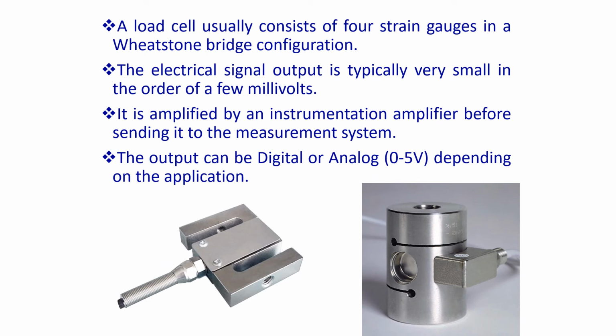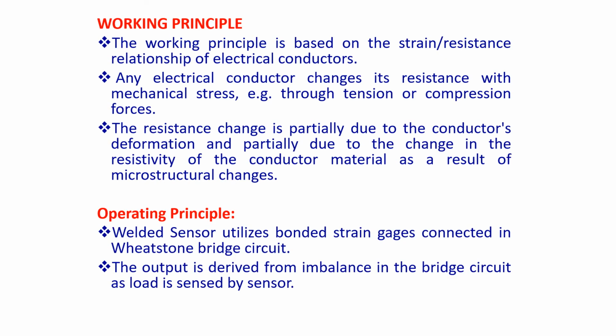If you look at this, we can see 4 strain gauges in a Wheatstone bridge configuration. The electrical signal output is typically very small, in the order of a few millivolts if we use only one strain gauge, so we use 4 strain gauges. The output can be digital or analog depending upon the application. The working principle of the strain gauge is that deformation results in a change in electrical resistance through tension or compression forces. The sensor utilizes bonded strain gauges connected in a Wheatstone bridge circuit. The output is derived from the imbalance of the bridge circuit as load is sensed by the sensor.